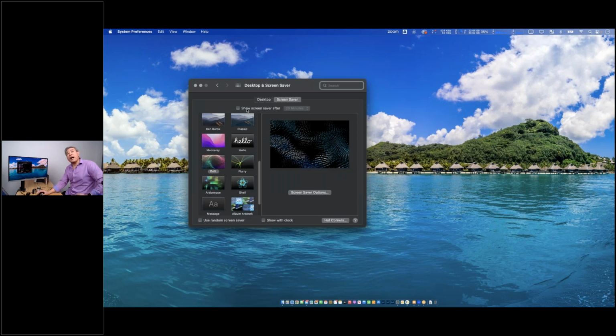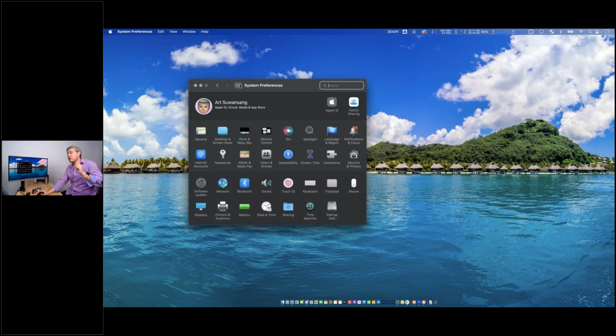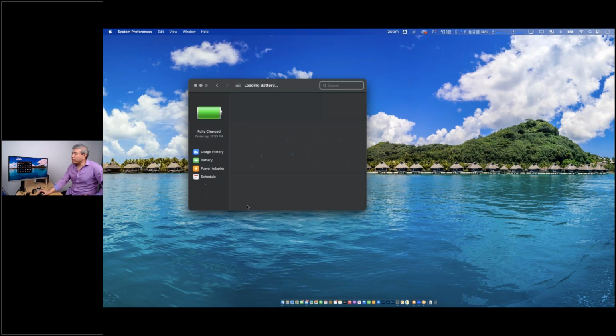Now, screensaver, I already have disabled this on mine as well. By default, Mac will have this box checked, and it will automatically come on after 20 minutes of mouse and keyboard being idle. I recommend turning this off. This way, if your calibration runs longer, the screensaver doesn't pop up in the middle of the calibration, ruining the calibration result. All right, and we're going to change one more setting on the machine, and that is under battery.